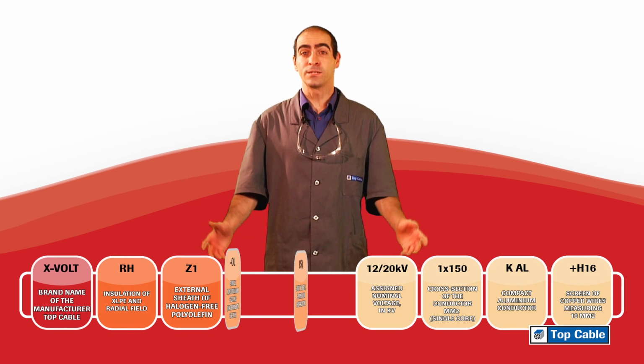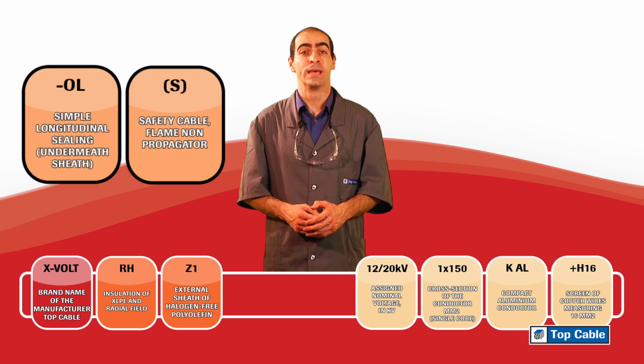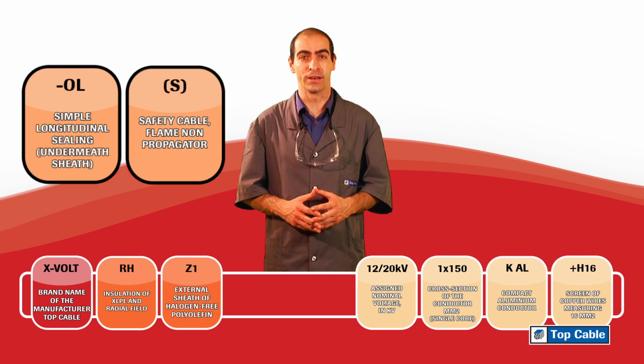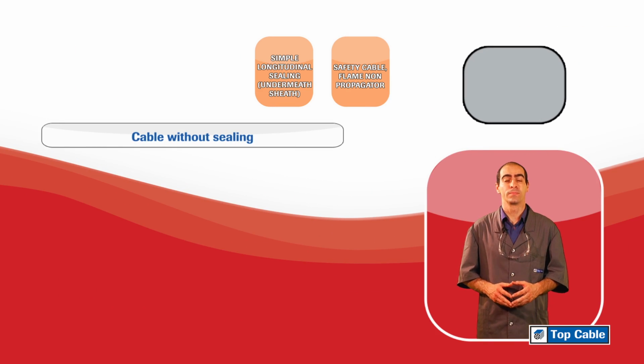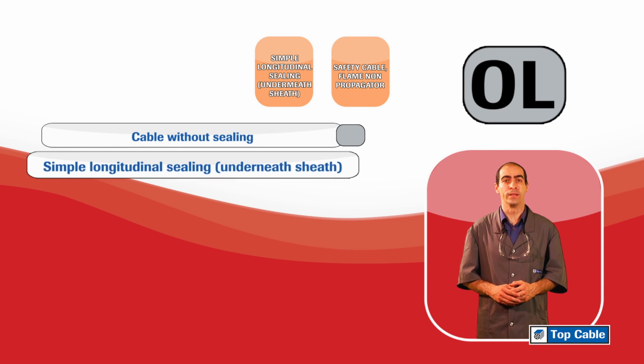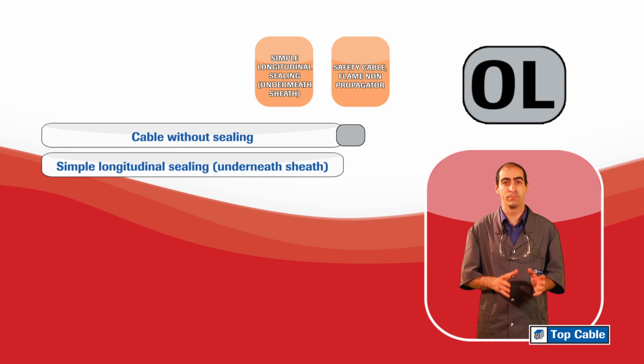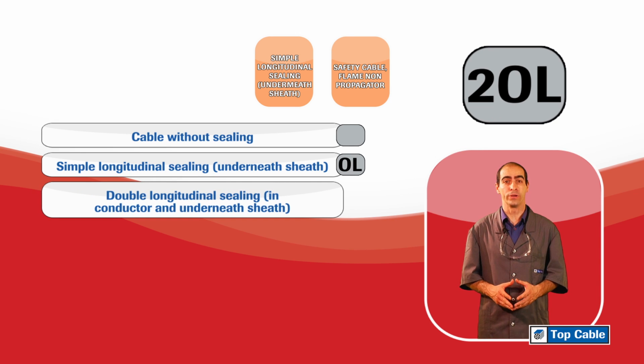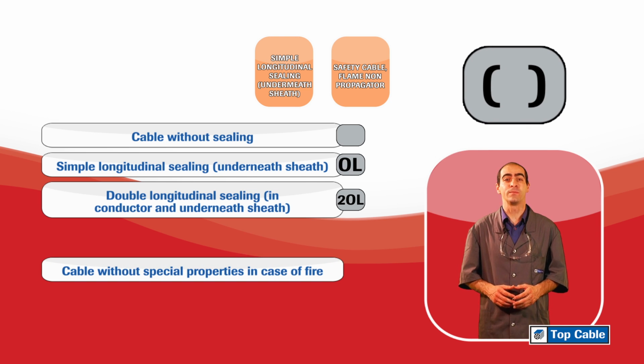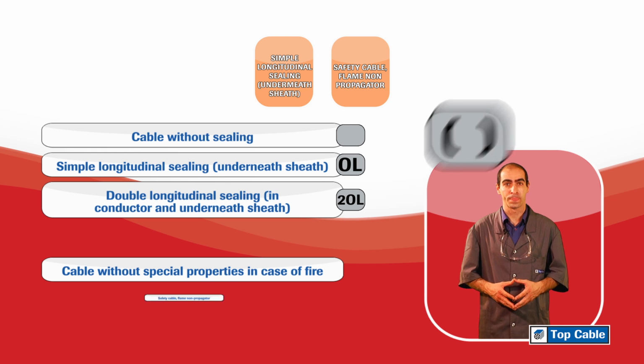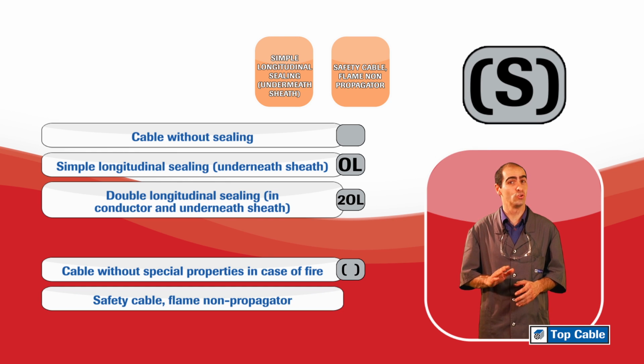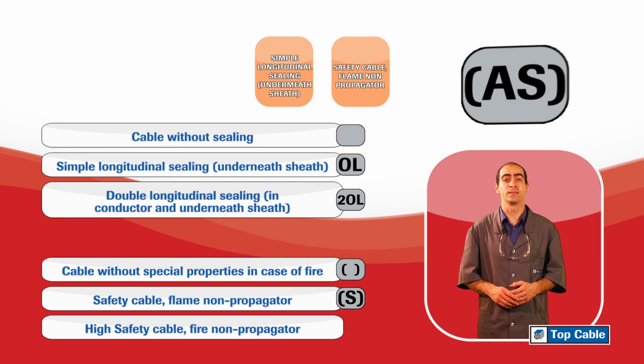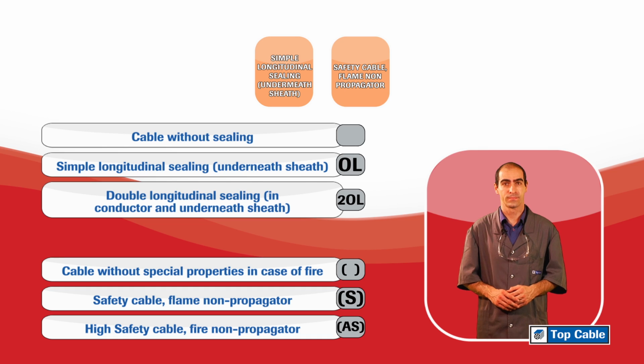The second block, OL, S in the example, refers to additional characteristics. In white, cable without sealing. OL, simple longitudinal sealing, underneath sheath. 2OL, double longitudinal sealing, in conductor and underneath sheath. In white, cable without special properties in case of fire. S, safety cable, flame non-propagator. AS, high safety cable, fire non-propagator.